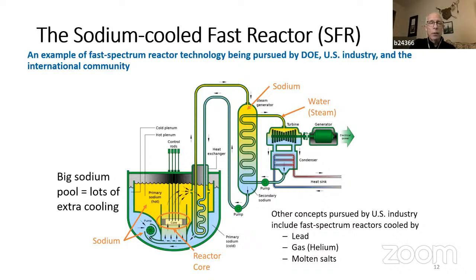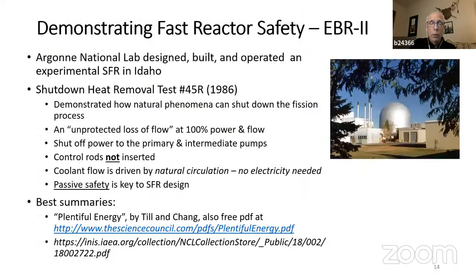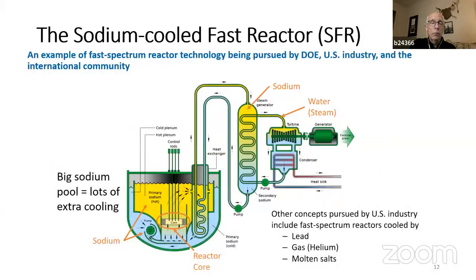What about zero gravity? Well, the lower the intensity of gravity, the bigger the separation you need. Actually, this diagram is a little bit misleading, Greg, because you always have the heat sink up high and the heat producer down low to get natural circulation. Think of your chimney, the fire's at the bottom of the chimney. Yeah, and that's your gravity gradient. Exactly. So this picture should actually show this, whoops, sorry. I've got a very sensitive trackpad on this new laptop. Normally the coils in this heat exchanger on the right would be inside the vessel, much higher. And that's where you get the natural circulation.